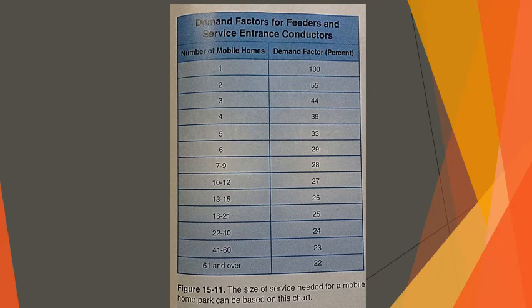This is the minimum. For example, assume that the largest mobile home that will fit in the park has a calculated load following section 550.18 that is less than 16,000 VA. Section 550.31 requires you to use at least 16,000 VA for each mobile home lot, or 16,000 VA times 25 equals 400,000 VA.